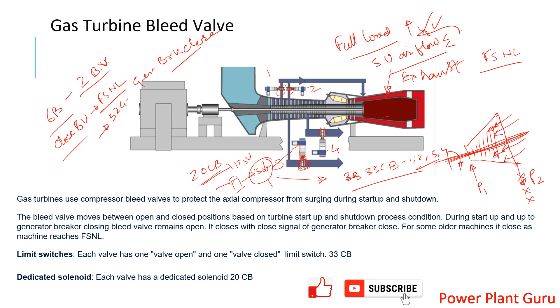To summarize: bleed valves are required to handle excess compressor air during startup and low-load conditions. The number of bleed valves may vary. They remain open during startup and close when the generator breaker closes. Similarly, during load reduction and shutdown, once the breaker opens, the bleed valve opens again and remains open while the machine shuts down.